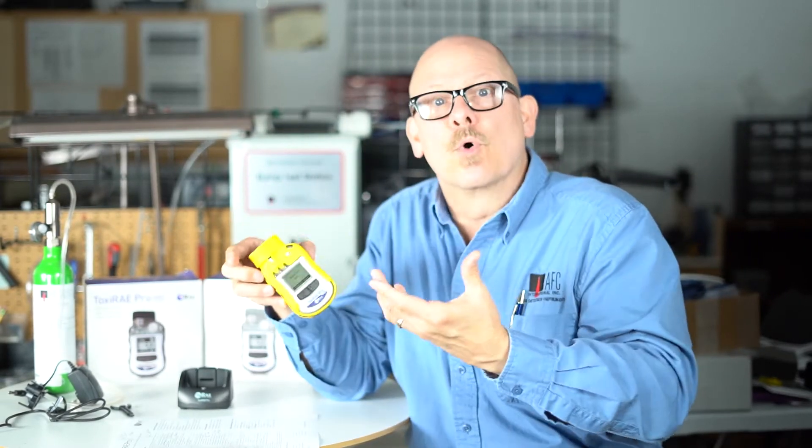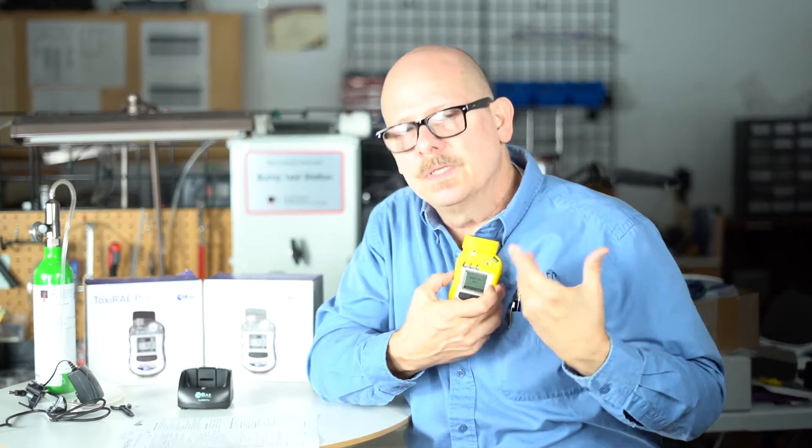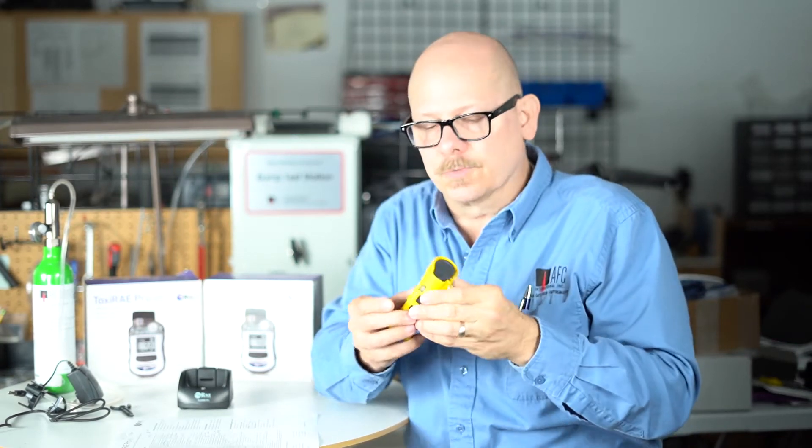This won't be used for confined space. You're going to be using it more for personal monitoring. You want to keep it in the breathing zone. Most of us breathe between here and here. So when we're working, it's actually taking a sample and protecting me, but also doing the data logging. It's going to be critical for the industrial hygienist and safety people involved with exposure monitoring.